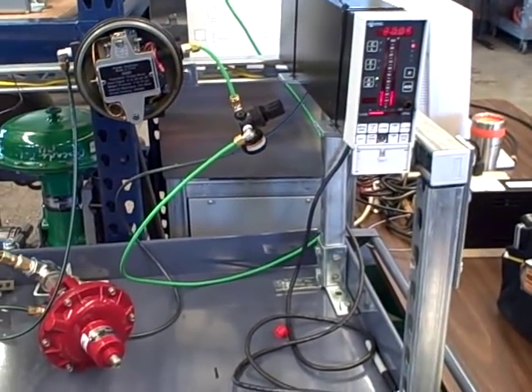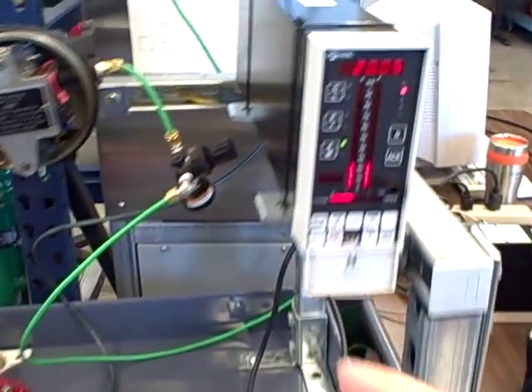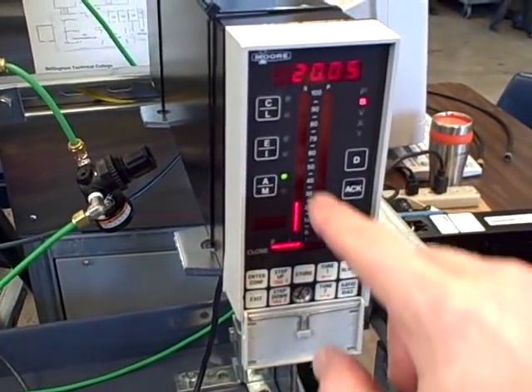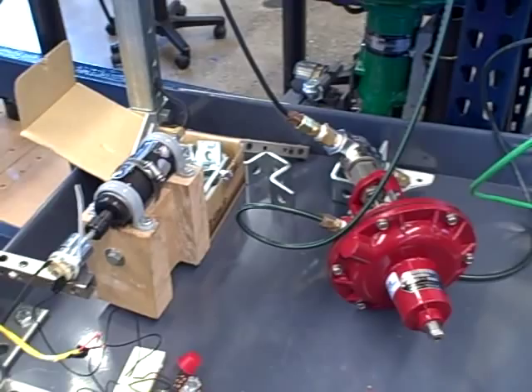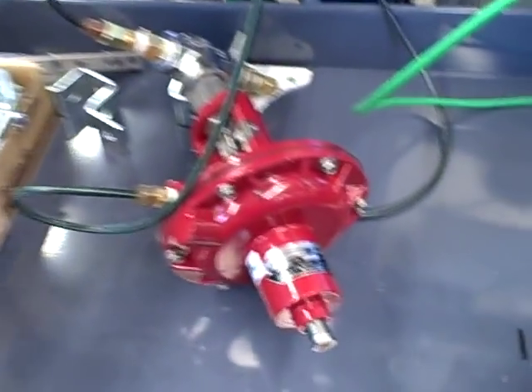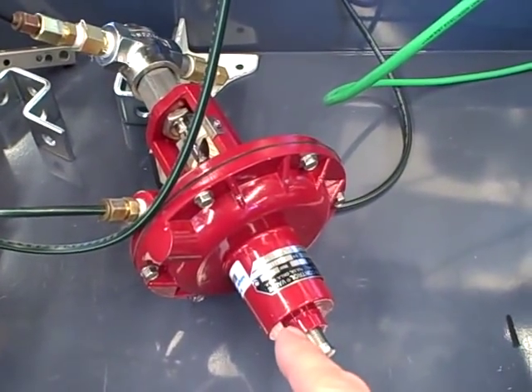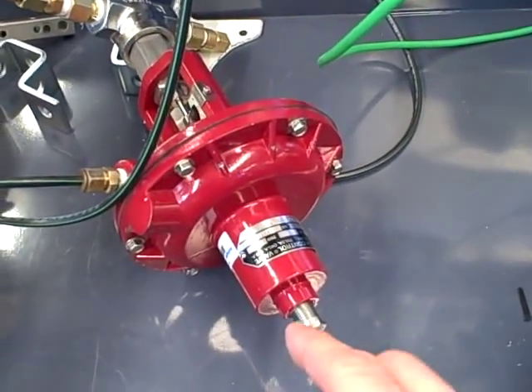When last we observed this process, we were having difficulty with the gain of the system. As we turned the set point down towards the low end of the range, we found we had a lot of oscillation. And the principal reason for that was our control valve was linear trim instead of being equal percent.